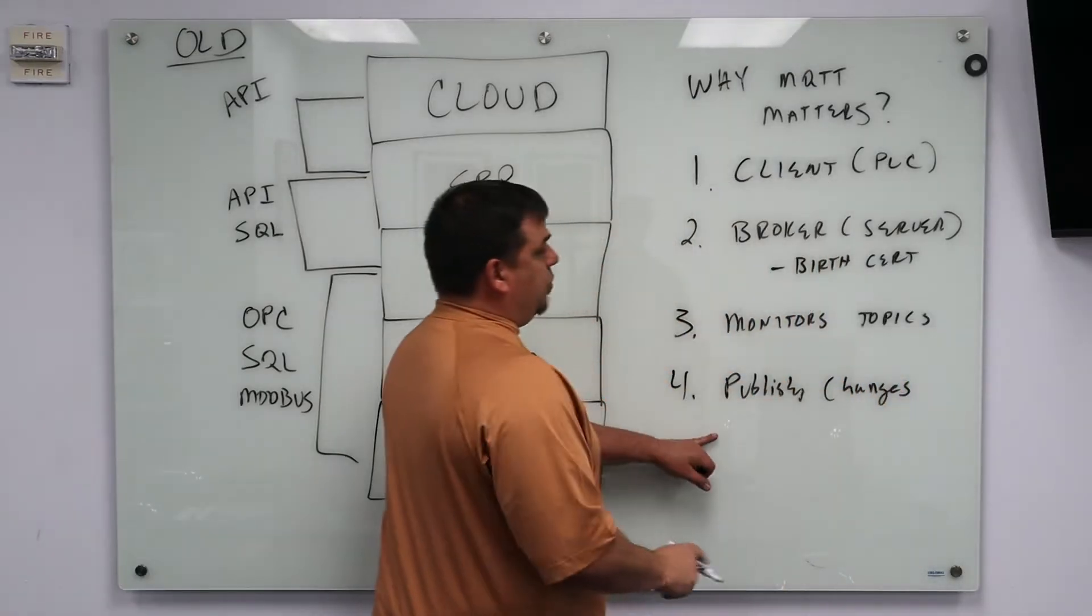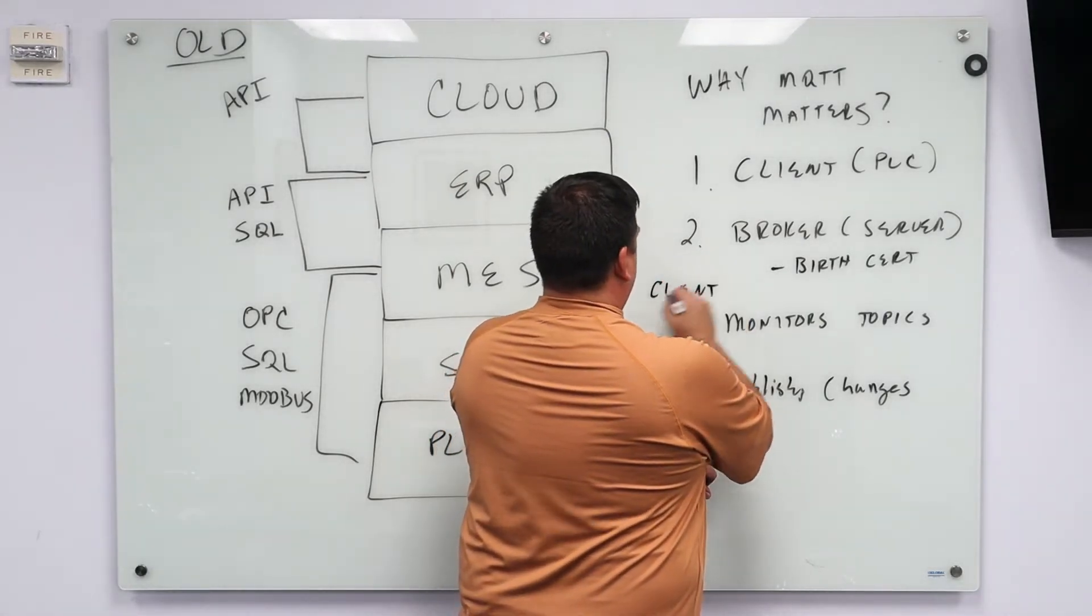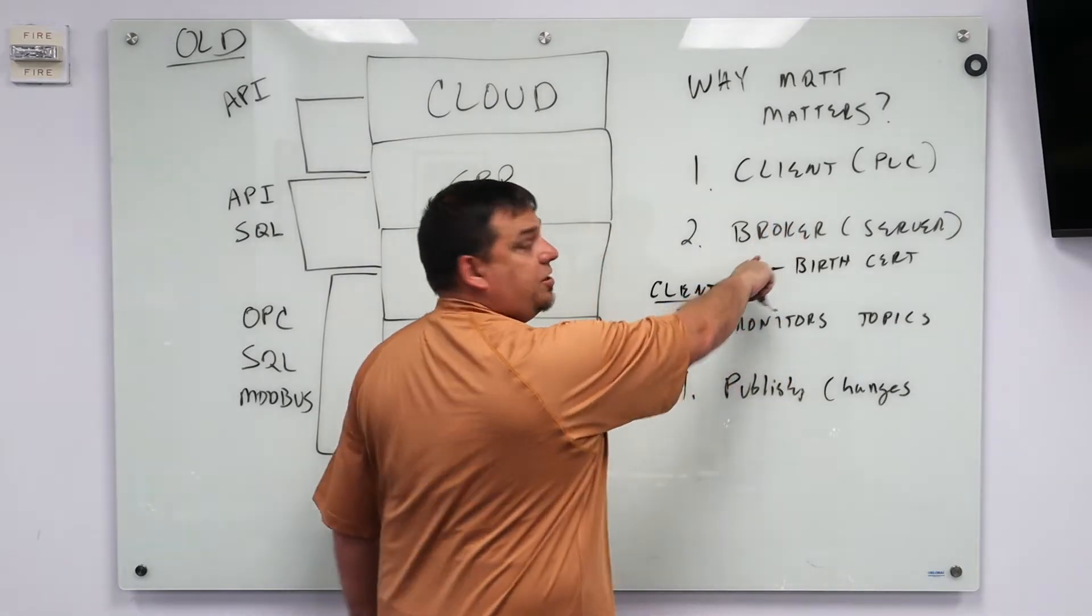So the PLC monitors its tags and monitors the topics and publishes changes. So what happens is when a tag changes, the client, this is all client stuff, it monitors the tag and then it publishes the change to the broker.